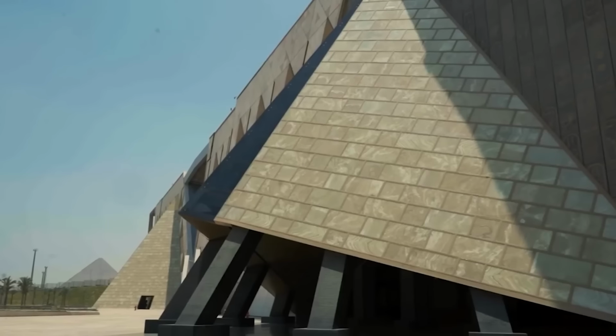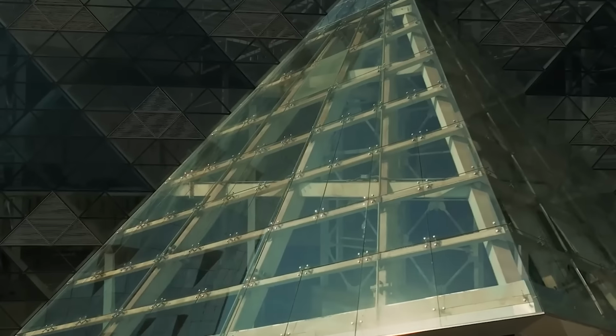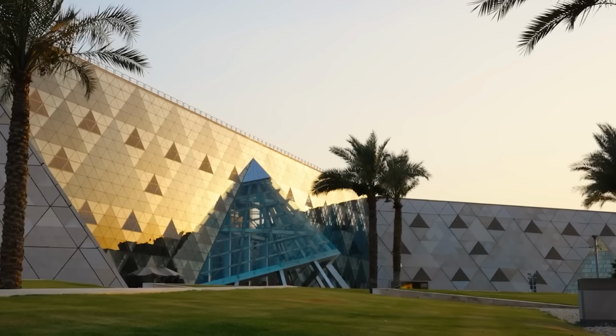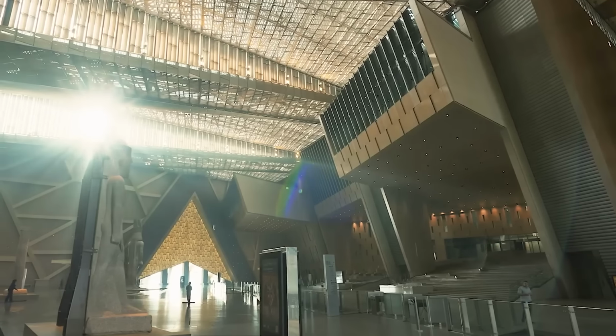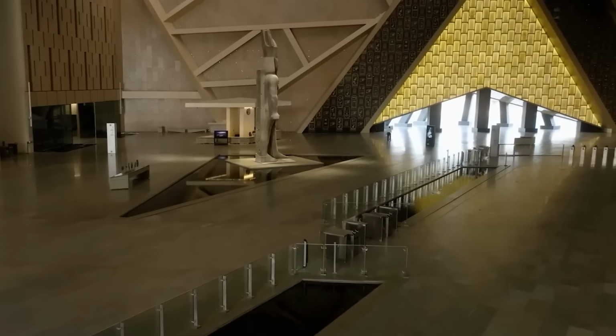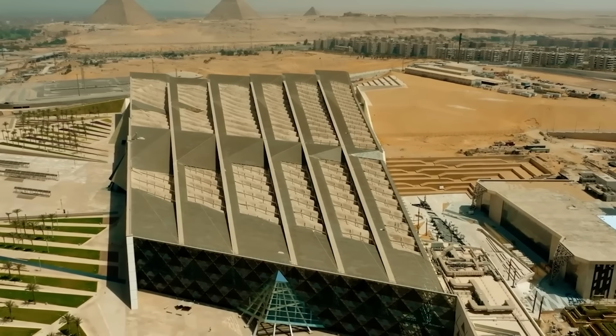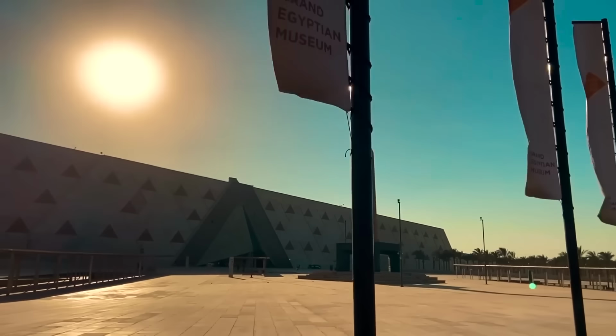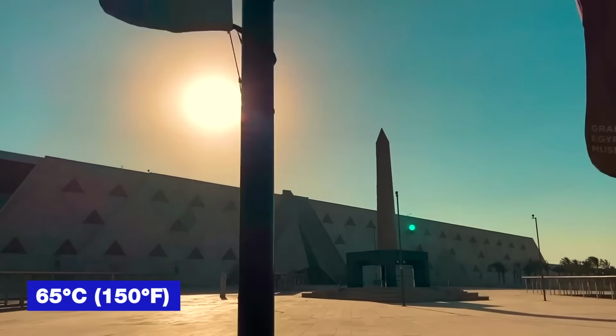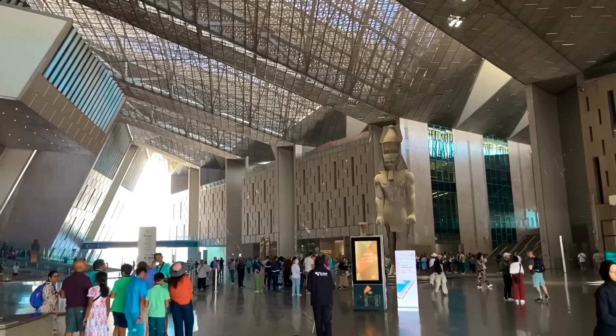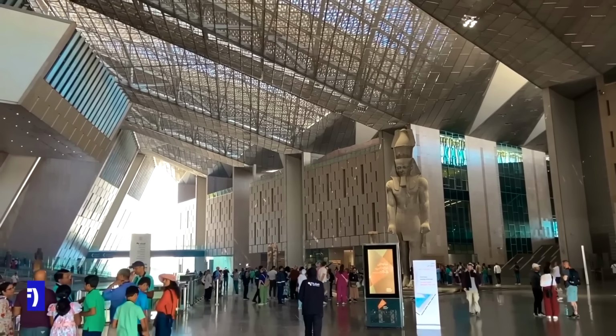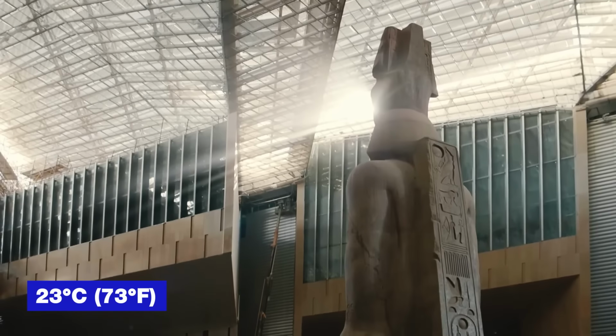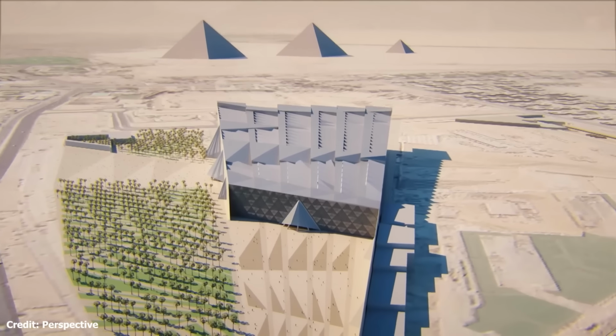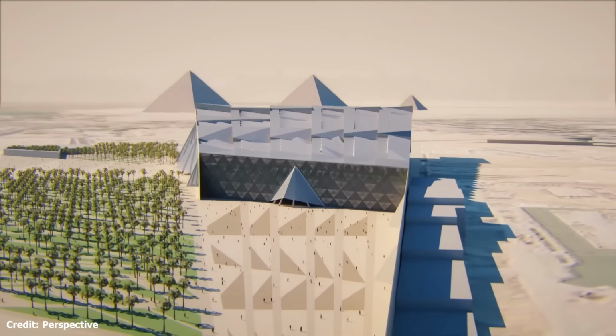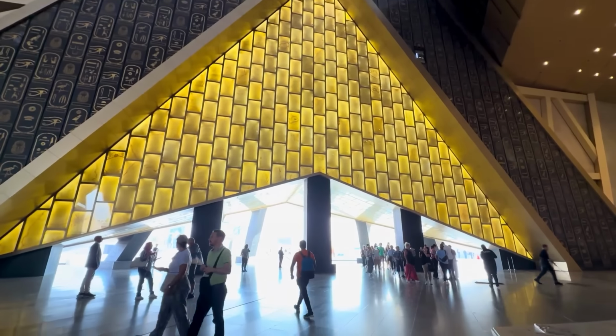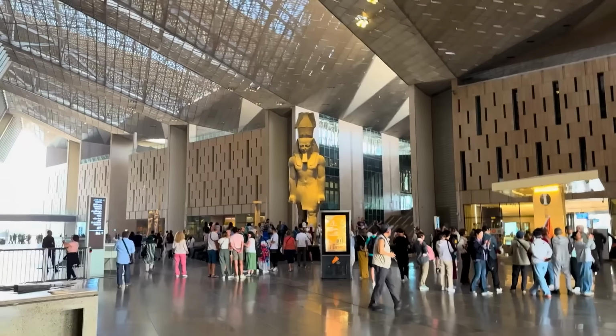While the museum's triangular glass facade may visually echo the pyramids, it's primarily a masterpiece of sustainable engineering. The angled facade is covered in high-performance glass that floods the interior with natural light while blocking harmful UV radiation and reducing thermal heat gain. Even when exterior temperatures soar to 65 degrees Celsius, 150 degrees Fahrenheit in the desert sun, the museum maintains a comfortable temperature inside of 23 degrees Celsius, 73 degrees Fahrenheit. This isn't achieved through brute force air conditioning. The building's thermal envelope, orientation, and natural ventilation strategies minimize cooling loads before mechanical systems even engage.